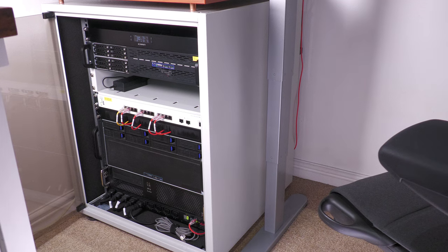Noise-wise, the fans are also really good. I think even on speed 1, they're slightly louder than my old fan. However, a fan cooling the rack isn't really a problem from a noise perspective, because it's quite a low frequency, broadband sound, so it's quite an easy-to-drown-out noise. It's just a sort of low hum. The problematic noise with server racks are things like servers that have little 40mm fans with a really high-pitched whine, and the rack really helps block those out, so the little hum from the rack cooling system is not a problem at all.